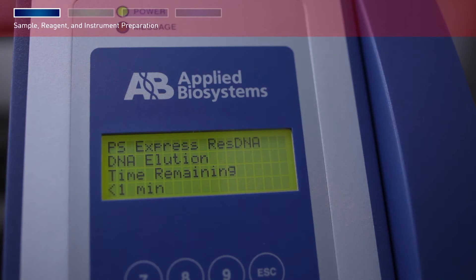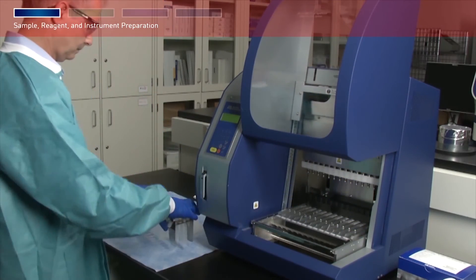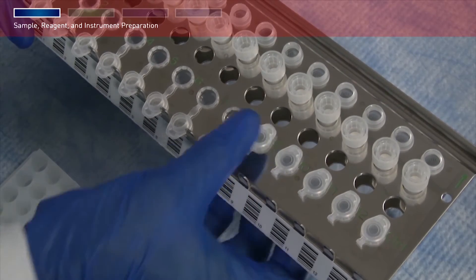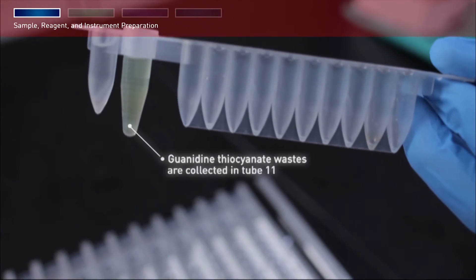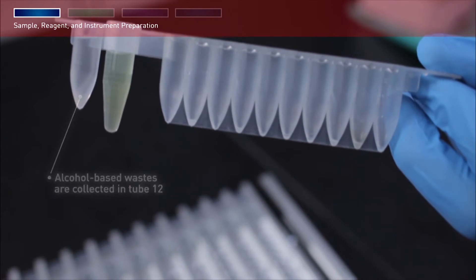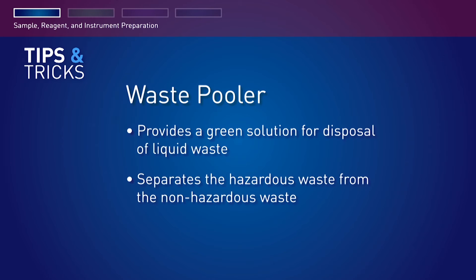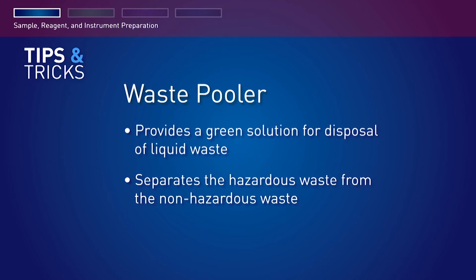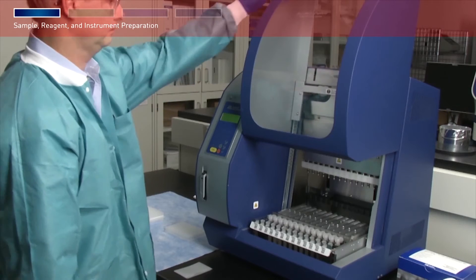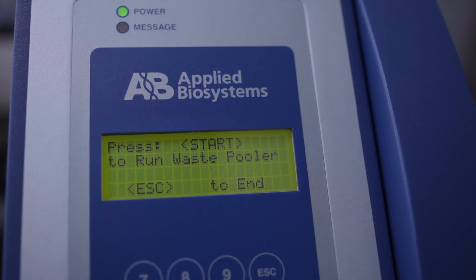At the end of the run, the instrument beeps briefly and the digital display shows additional options. Open the instrument door, remove and cap the elution tubes containing the purified nucleic acid. If you ran the waste pooler protocol, the guanidine thiocyanate wastes are collected in tube 11 and the alcohol-based wastes are collected in tube 12, leaving the rest of the cartridge empty and easy to dispose. The waste pooler provides a green solution for disposal of liquid waste generated from an Automate Express run. The waste pooler separates the hazardous waste from the non-hazardous waste and consolidates it, thereby enabling a safer and easier way to dispose the spent reagents.